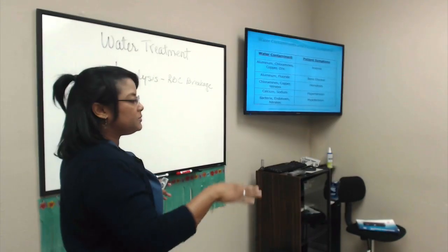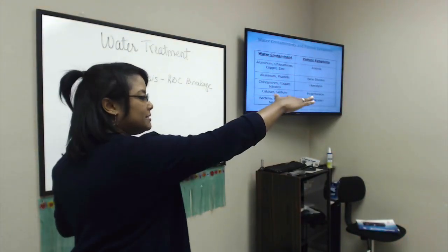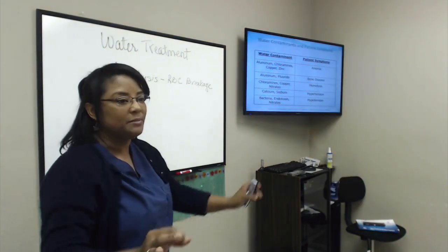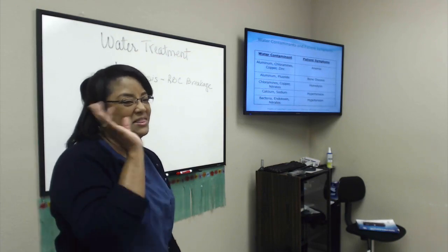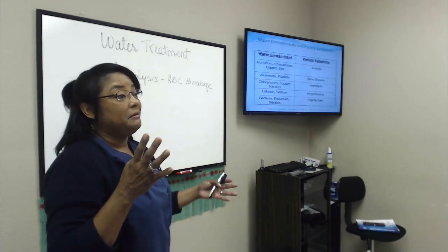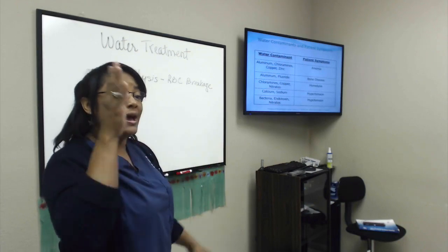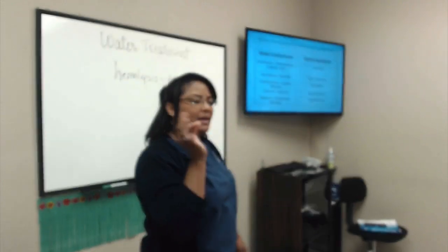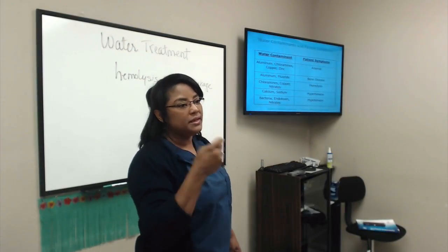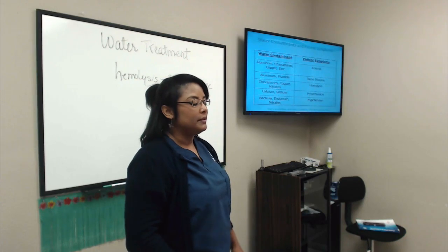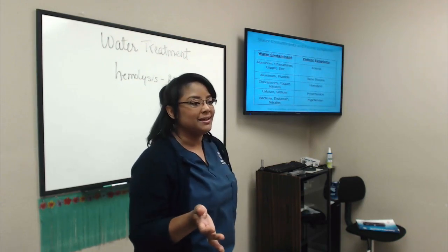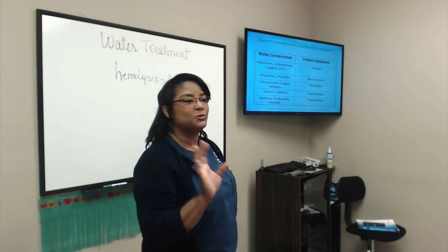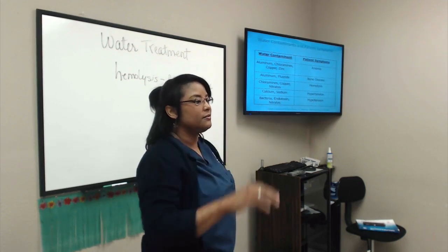And all of a sudden you see all of the patients on this side, they all start presenting hypotension at the same time. Not even think about it, right? If that happens, if you have a bunch of patients presenting the same symptom at the same time, we think it's water, something with the water. You don't have to know what it is exactly, but it's the water, okay? Usually it's the water. In that case, you turn off those machines, turn off, all of them.